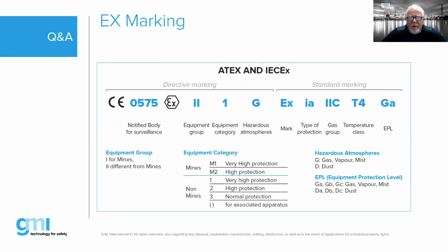So on the left-hand side, under the bracket, you see directive marking. The CE mark is conformity. The 0575 is the number for the particular notified body, the testing lab, if you will, that did the certification. The hexagon EX is telling you it's compliance to the ATEX directive. You have to have that hexagon with the CE mark in order to be compliant to the ATEX directive. Then you have a Roman numeral 2, a number 1, and a G. The Roman numeral 2 is equipment group, and that's telling us it's a surface area application equipment group. So anything that's above ground is going to be Roman numeral 2. Equipment category 1 is telling us it's a double fault tolerant type product, but more or less, it equates to zone 0, and G is for gas applications.